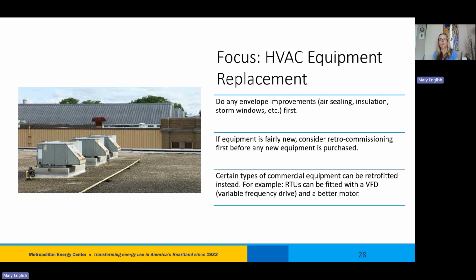I worked for a company where RTUs could be retrofitted with a variable frequency drive and this electronically commutated motor, and they would see their return on investment in less than two years, sometimes even a year, with these improvements on their rooftop units. So talk to your facility manager or a professional and see what might be done rather than a complete HVAC equipment replacement. But if you do go for a complete equipment replacement, make sure your envelope and ductwork are addressed before you pick your equipment.